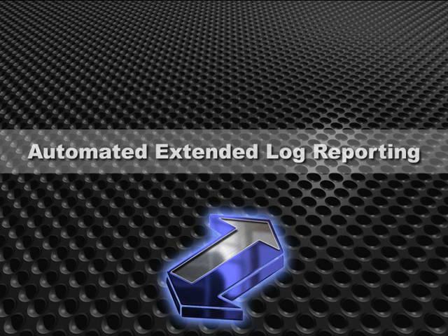So now you've seen an alternative to creating what can amount to be hundreds of programs on a large site. Instead, you can just drag points into Continuum groups, add a line to your batch file that's scheduled via Windows Scheduler, and your logs are created daily for you. In addition, Reports doesn't require Continuum to be running. That means that you won't lose the logs if Continuum isn't running for some reason. The logging role can even be delegated to any workstation on the network and be configured in redundant ways.